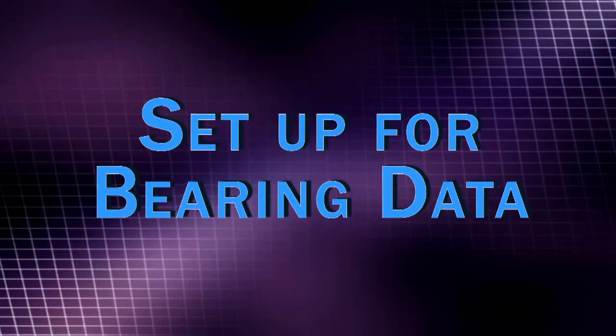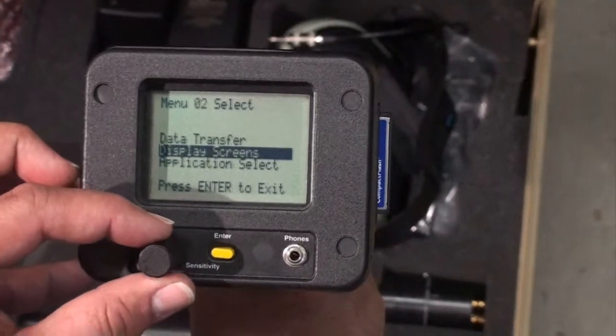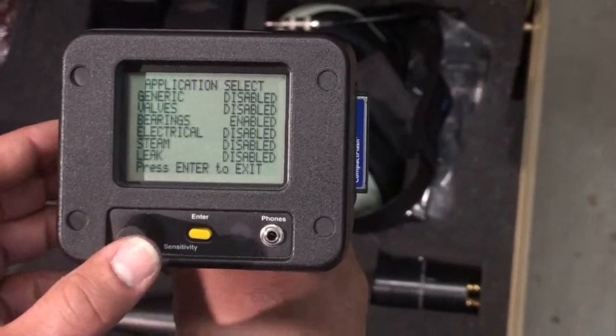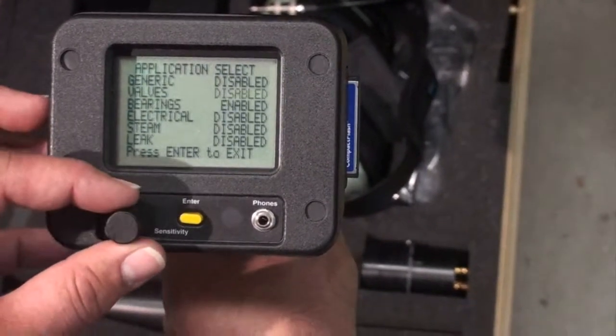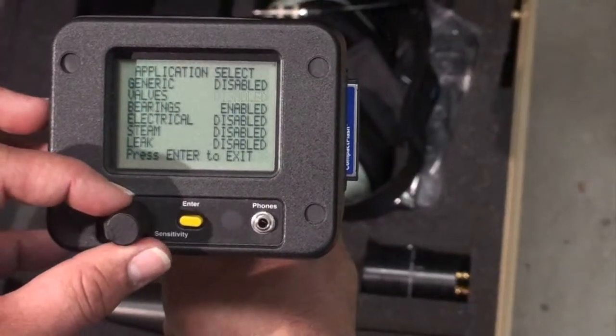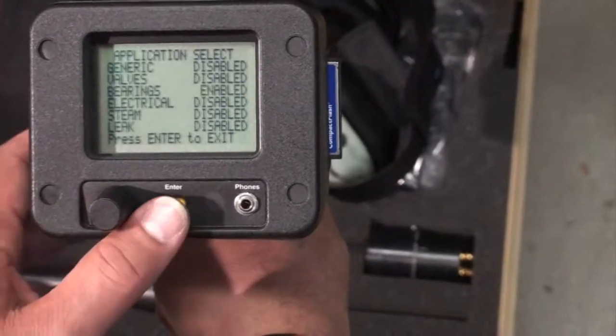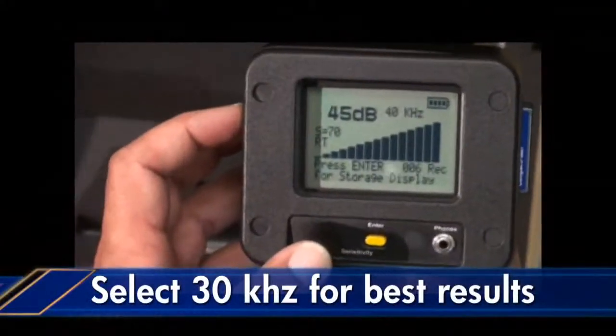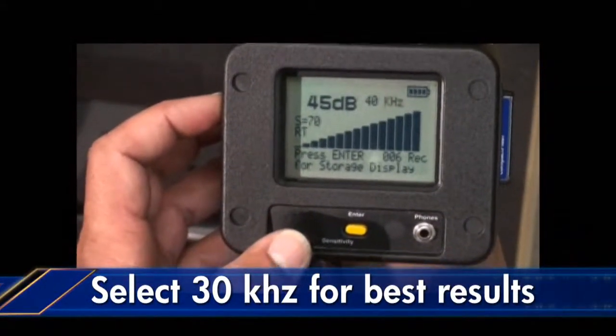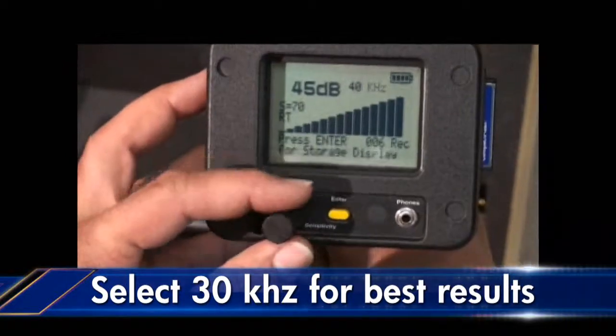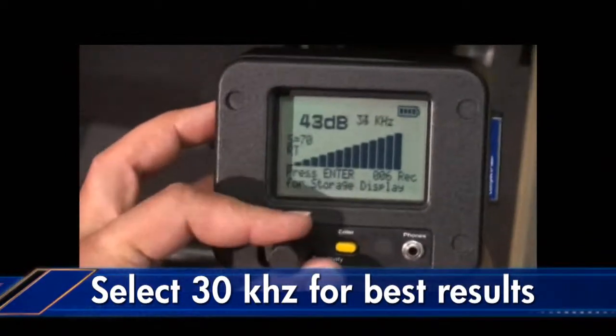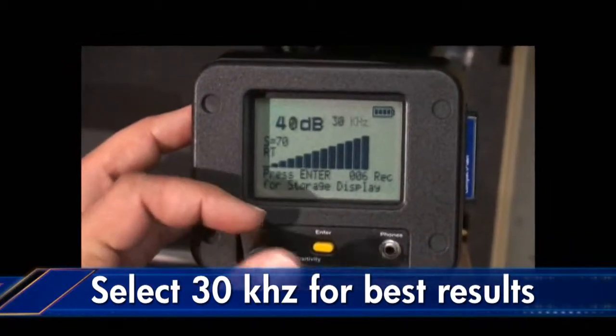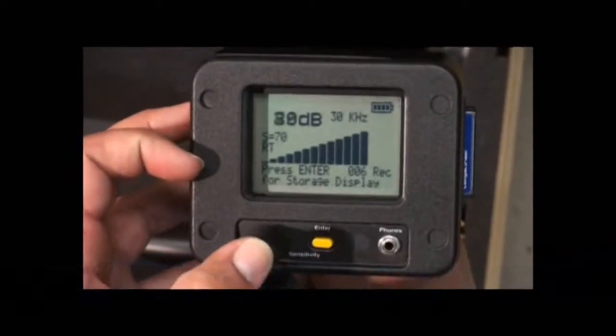First, open the application select menu and select the bearing application. Next, we'll use 30 kilohertz for best results when testing mechanical equipment. Here we're spinning down to 30 kilohertz and we're going to select it as demonstrated.